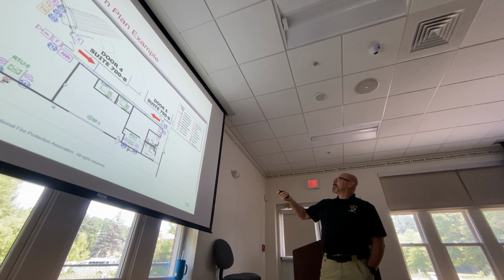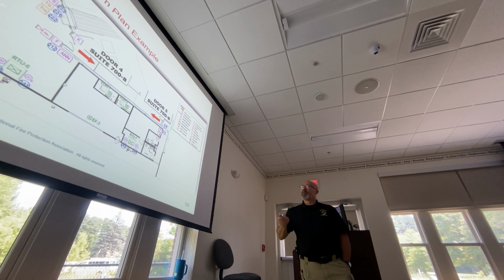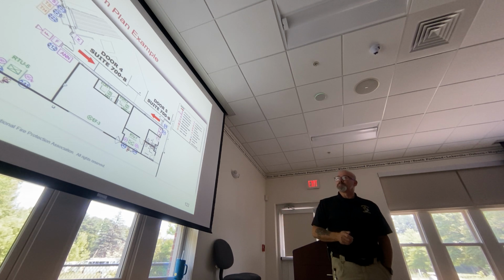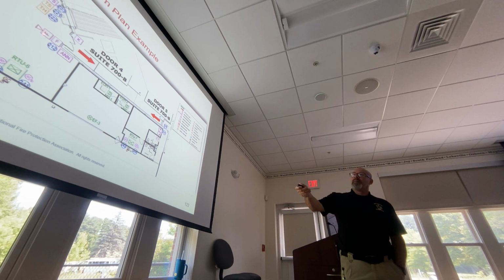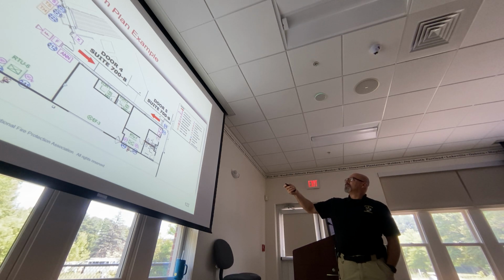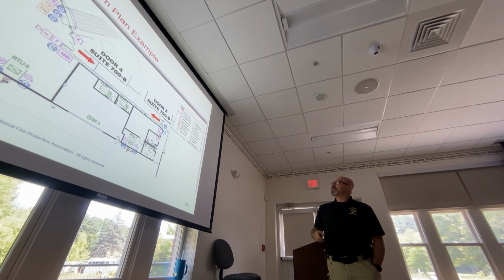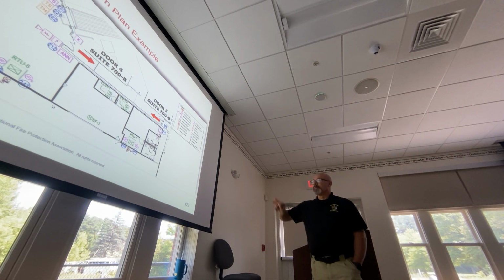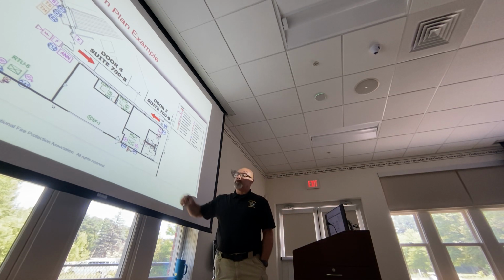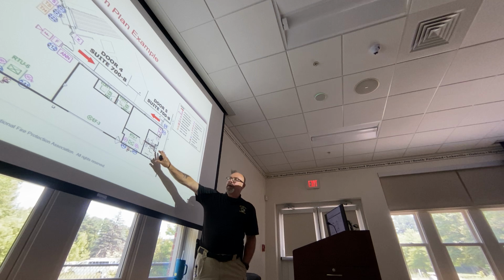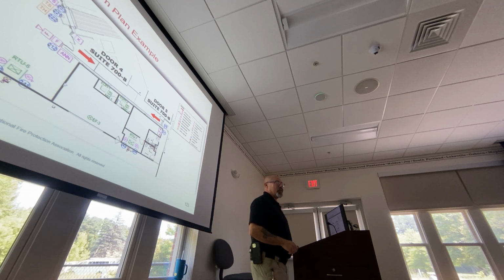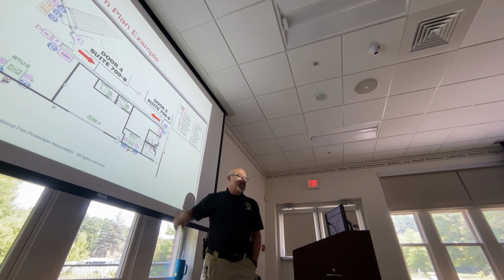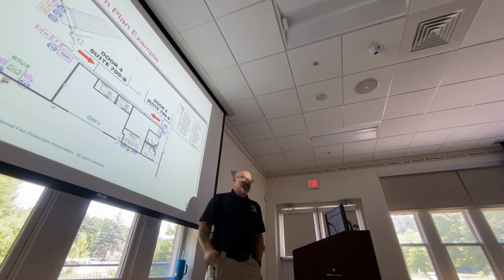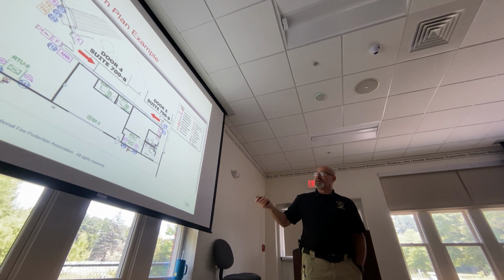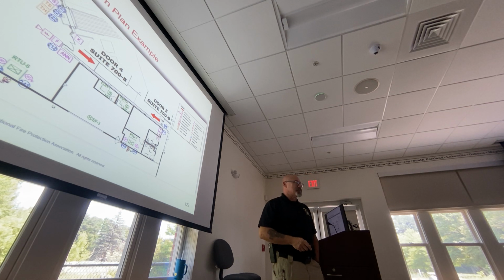FCPS looks like a booster panel, probably for a booster pump for the sprinkler system. F with a triangle, ADA horn strobe device. Okay, set of plans. This is very common. Most of the time, Josh and I don't get plans that say all that stuff on it when we get a building that has a fire alarm system in it. So we have to send a deficiency list out. Please provide a set of drawings indicating location of the fire alarm devices.